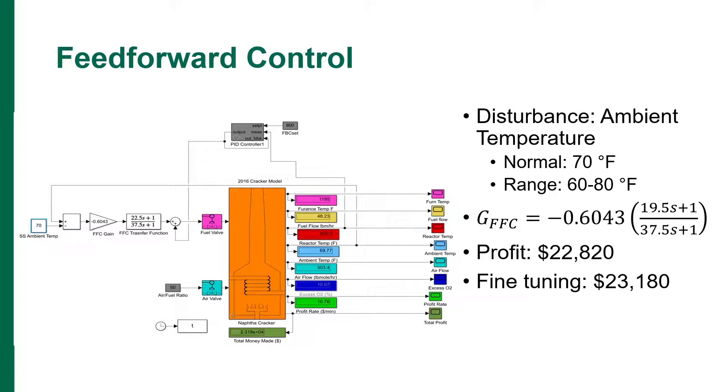The primary disturbances, in this case the ambient temperature, was occurring at a frequency which did not allow the system to settle down, namely due to thunderstorms and other factors. So we had to identify two models by determining how a change in the disturbance variable affected the output. Initially we selected a time when there was a step change in the ambient temperature and performed an identification test, which allowed us to obtain a transfer function for the load response.